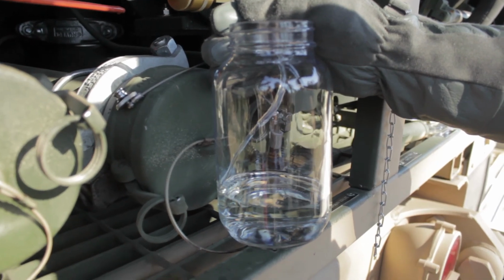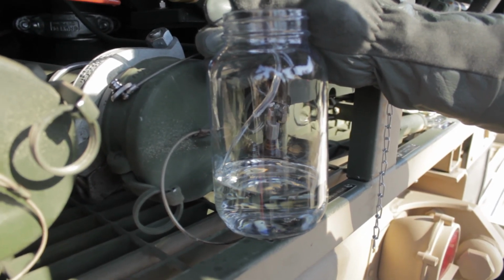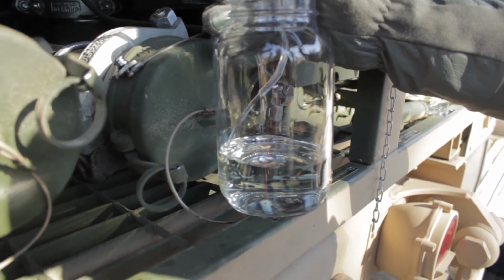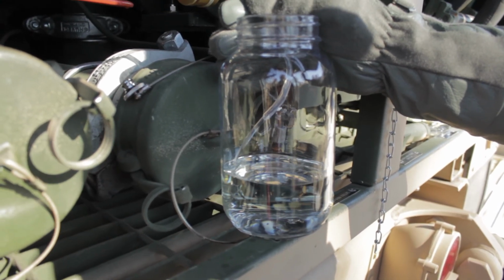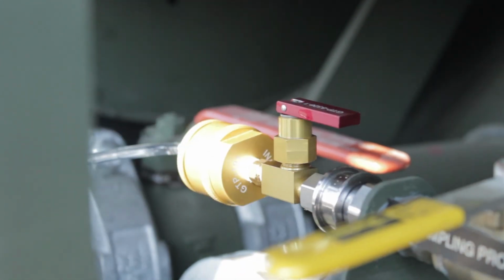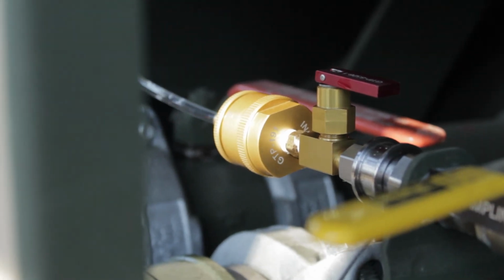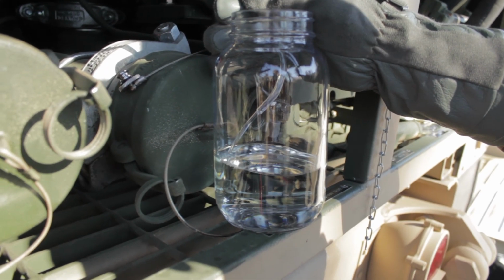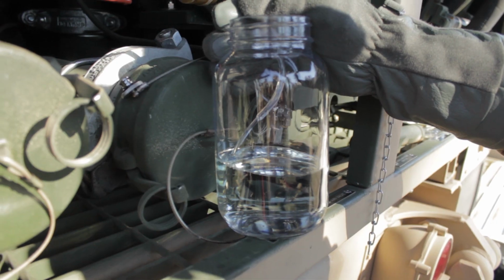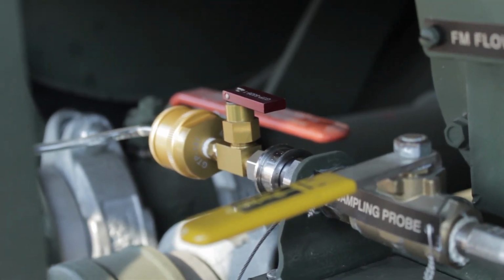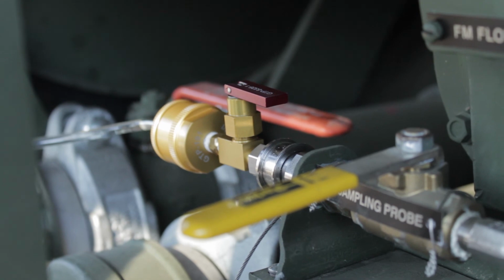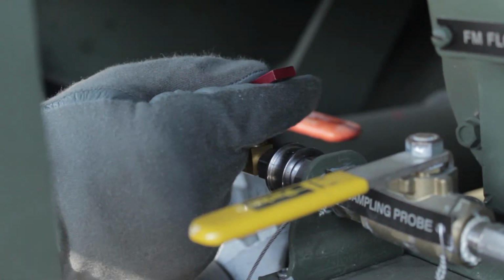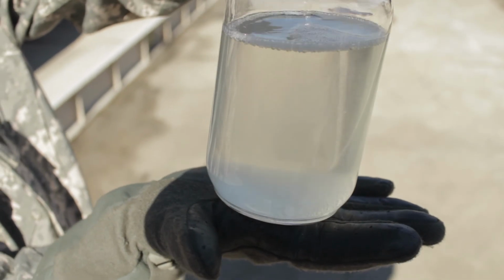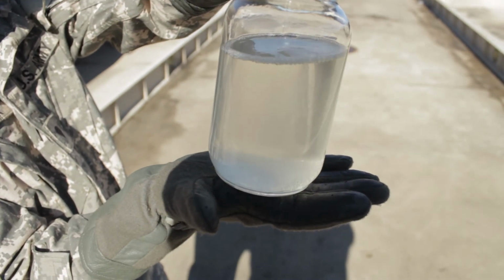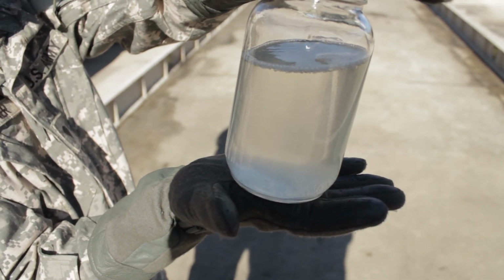To perform a visual examination of fuel, ensure the plastic discharge tube of the fuel sampling test adapter is put into a clear glass container. Move the toggle valve on the sample test probe to the open position and connector to the open position, parallel to the line. Fill the glass container to approximately 3/4 full. Move the toggle valve on the sample test probe to the closed position and connector to the closed position, perpendicular to the line. Put a cap on the clear glass container. Observe the fuel for color and appearance, visual examination.